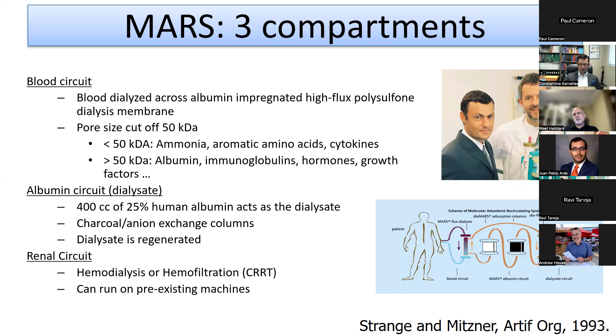So MARS has probably been around the longest, and generally this is blood being dialyzed across an albumin impregnated membrane with a low pore size. And as I mentioned before, the benefit is trying to remove aromatic amino acids, cytokines, and ammonia. The ammonia is removed because it piggybacks onto a renal replacement therapy circuit. It has an albumin dialysate, and that albumin dialysate is regenerated over a charcoal and anion exchange column. And then it can be run essentially on either hemodialysis or hemofiltration. Generally, how we were running this was on a Prismaflex circuit, and it can be run on CVVH or CVVHDF.